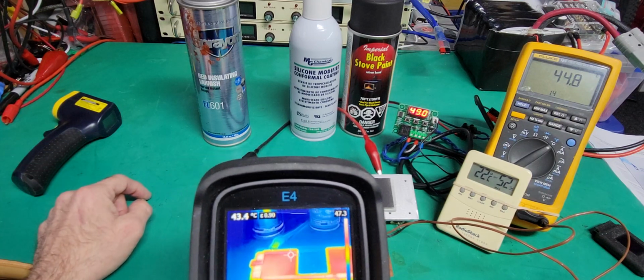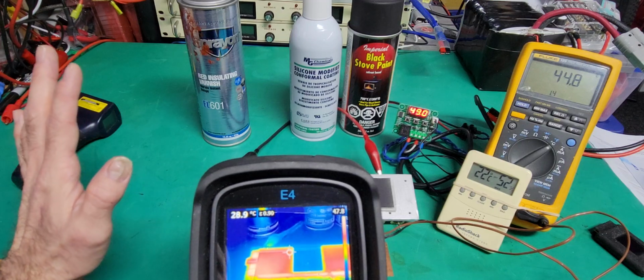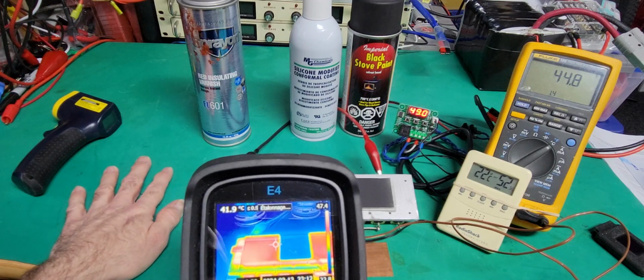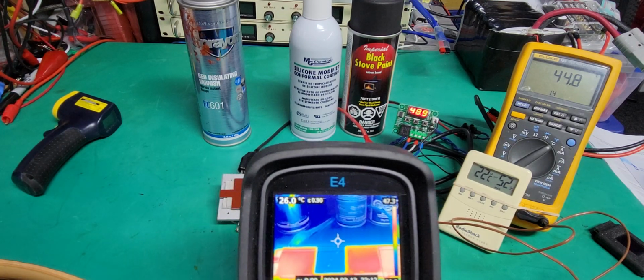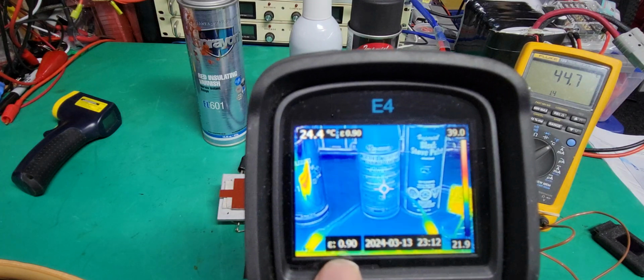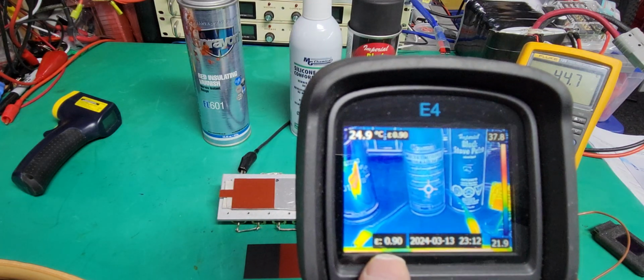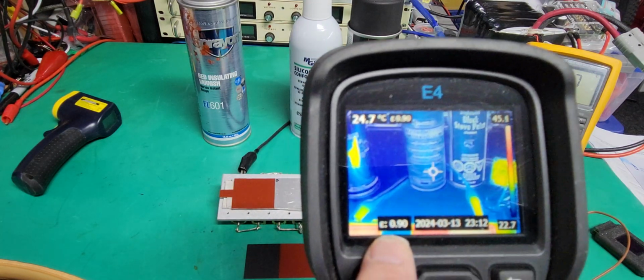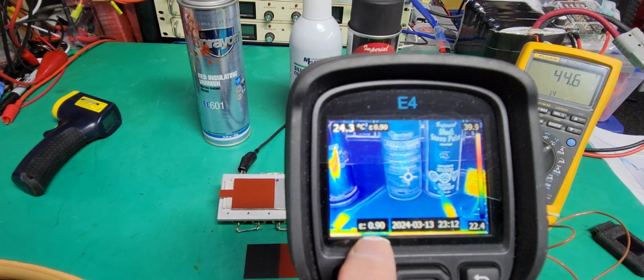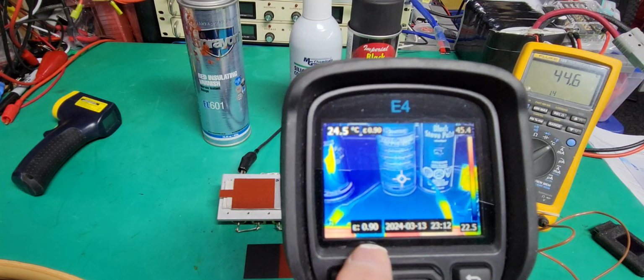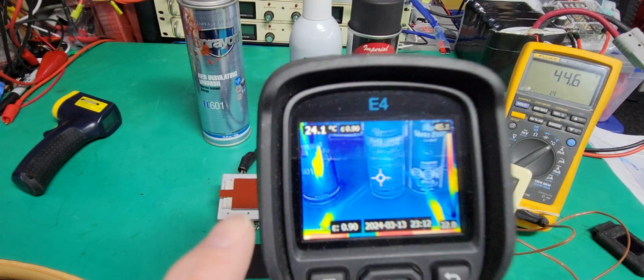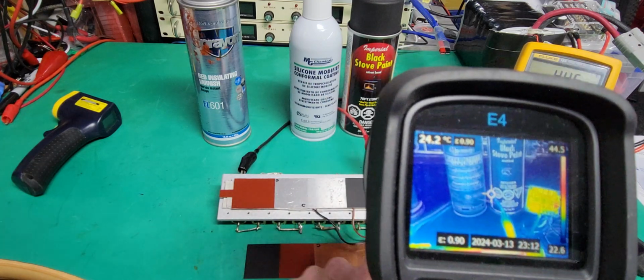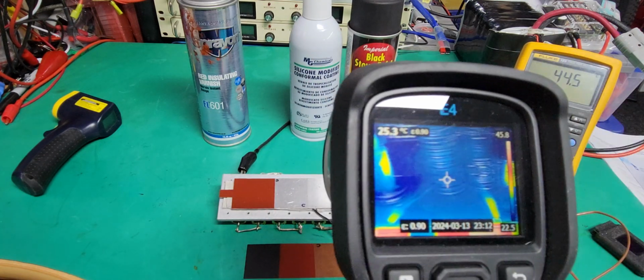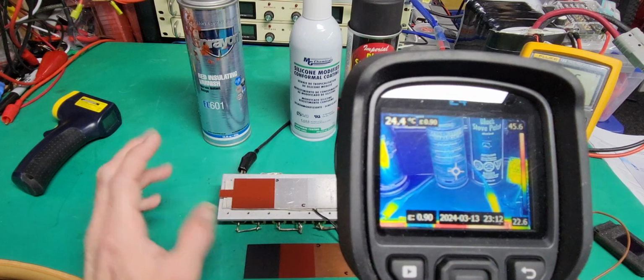So that's something to take very seriously, because you will get your measurement wrong. What you see on the camera here is the little epsilon. It's called emissivity, that's the symbol for it, and it's set at 0.9. So the temperature reading of this camera will be right if the emissivity of the surface is 0.9 or close to.